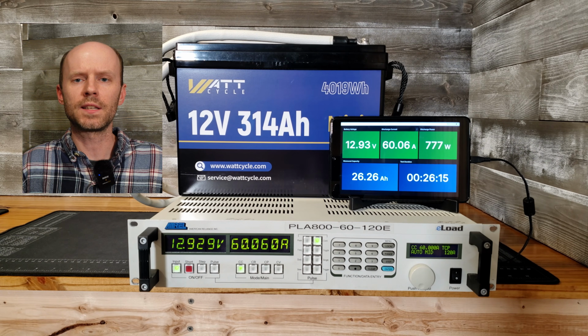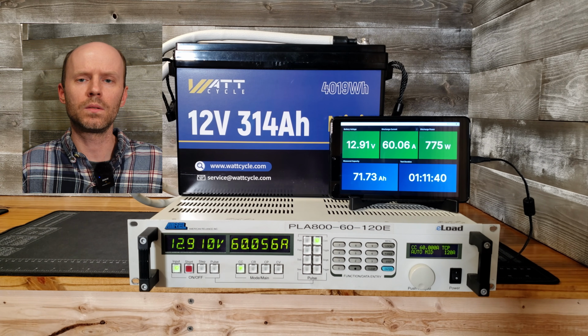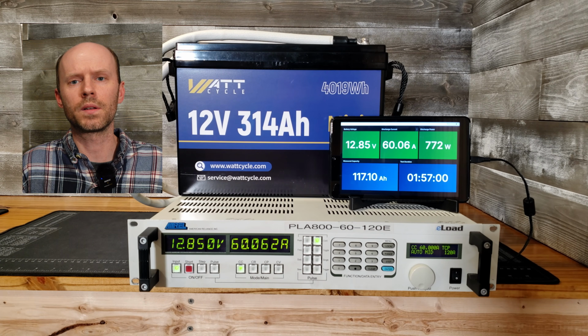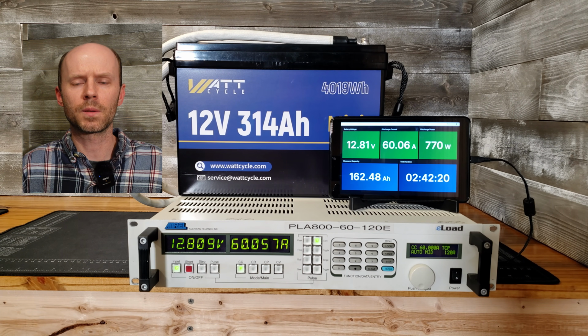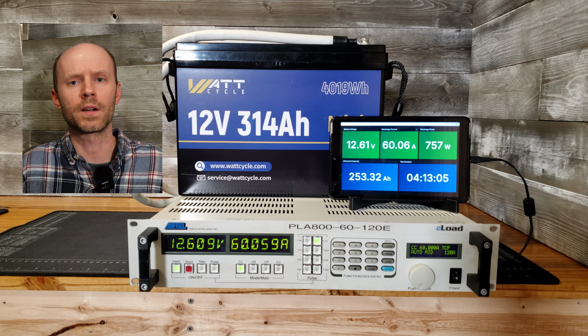I ran a capacity test using my American Reliance electronic load at 60 amps, or a 0.19 C rate. The measured capacity was 322 amp hours, or 2.5% higher than advertised.